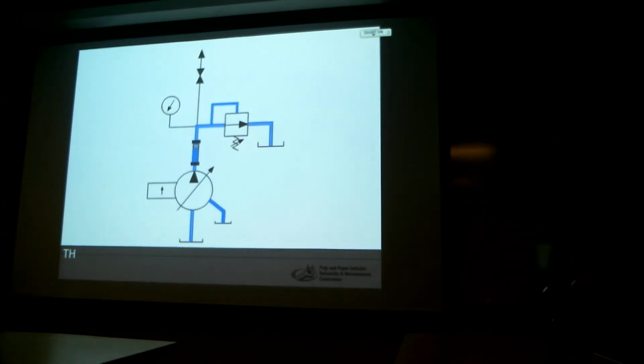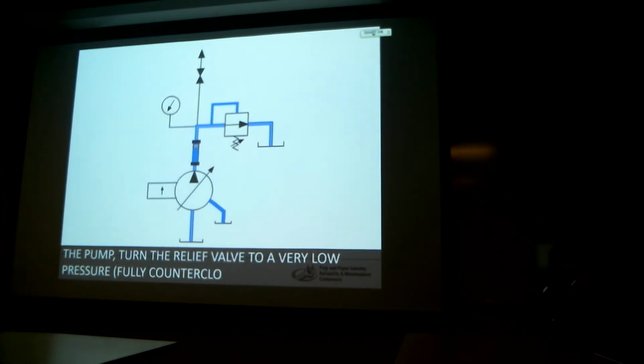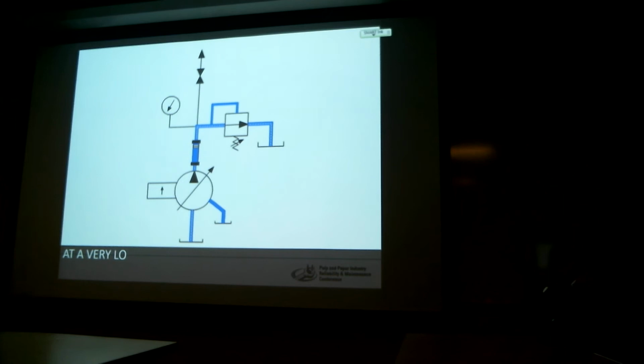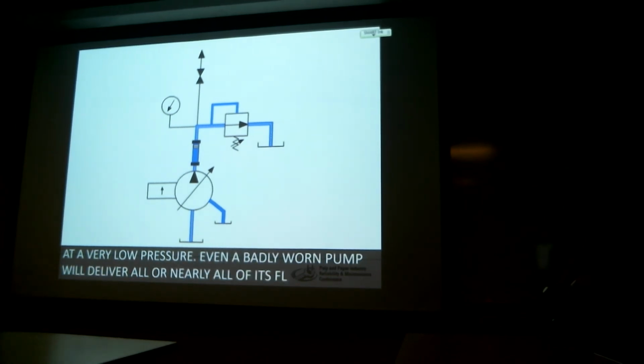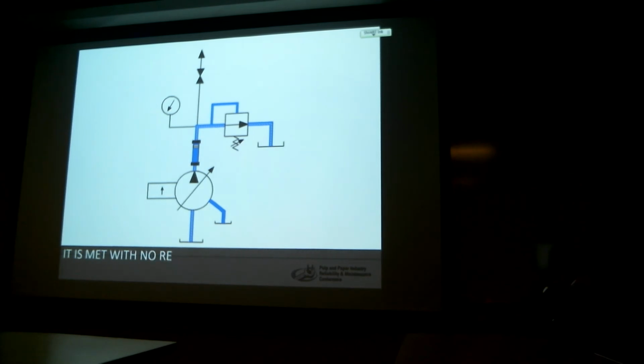Before starting the pump, turn the relief valve adjustment to a very low pressure, fully counterclockwise until no spring tension is felt. When the pump is turned on, it will deliver its flow across the relief valve at a very low pressure. Even a badly worn pump will deliver all or nearly all of its flow when it's met with no resistance.